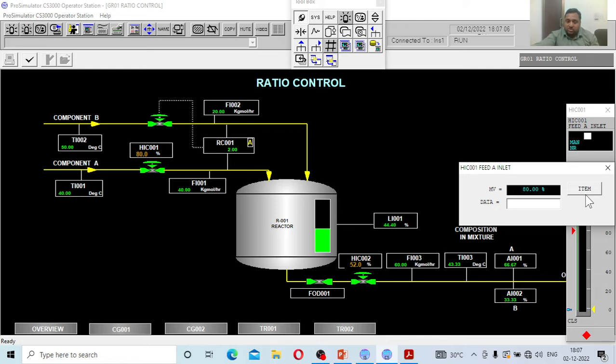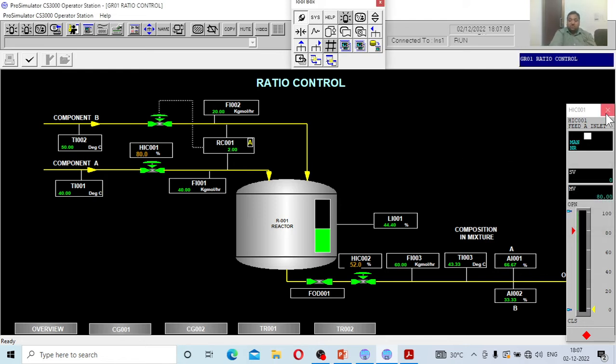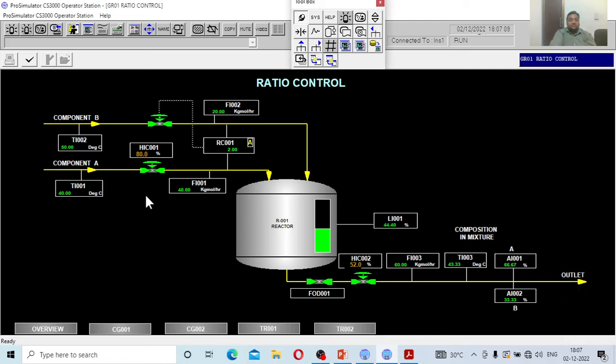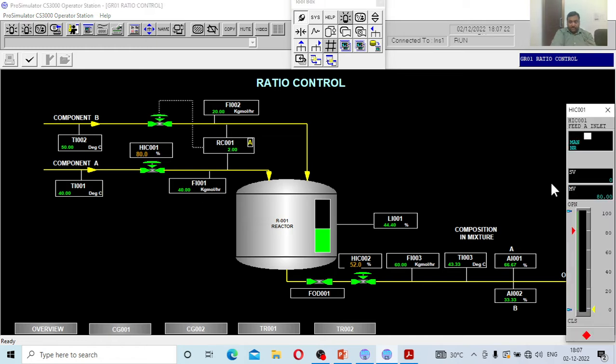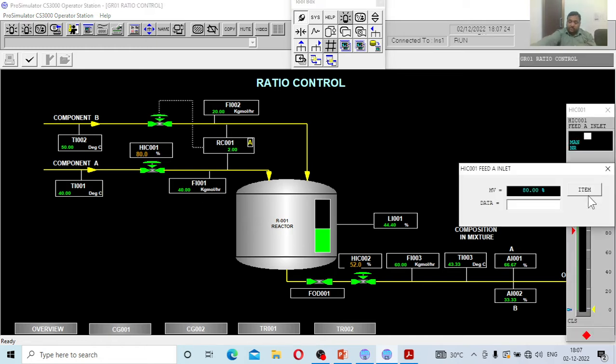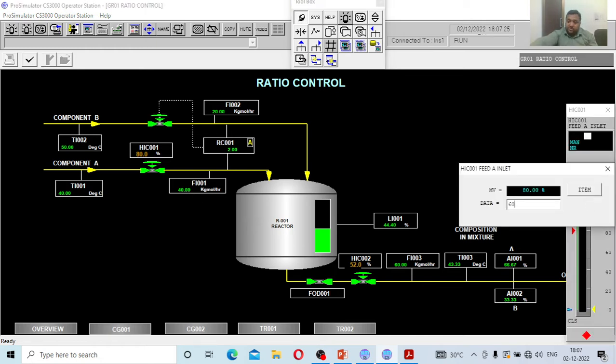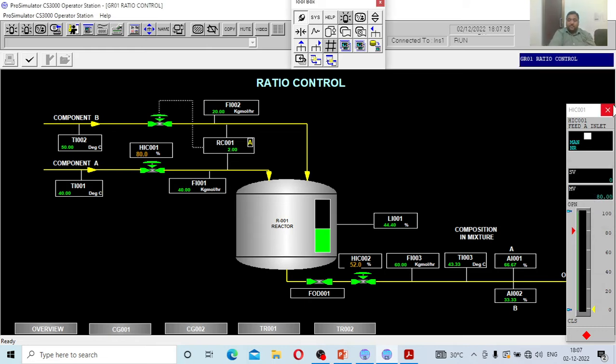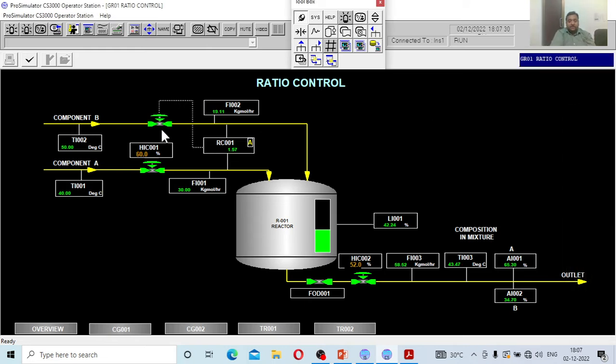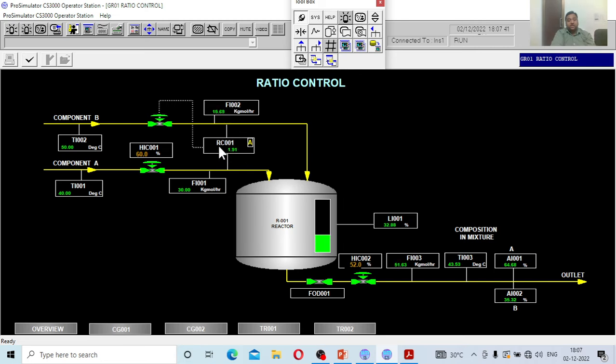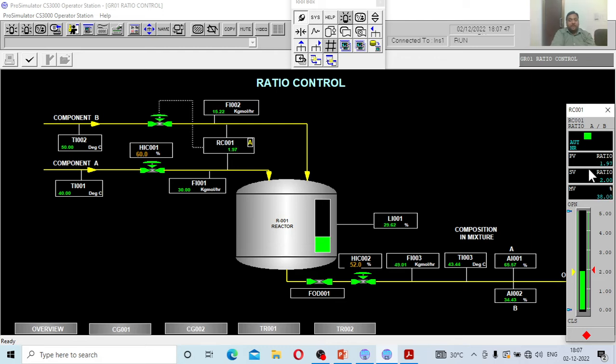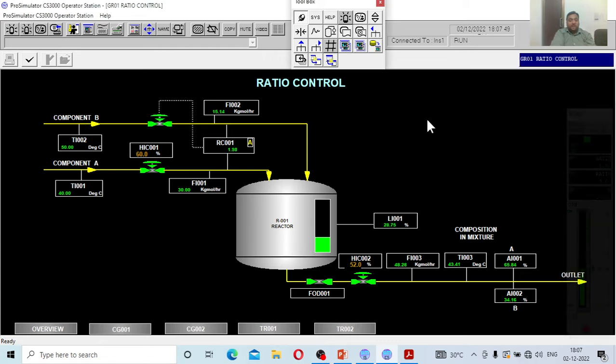What do you have to observe? Whether it is maintaining the same percentage, whether if I reduce A, is the amount of B also getting reduced stoichiometrically through the ratio controller. Let me reduce to 60 percent and see each parameter. The flow rate of A has been reduced to 30, accordingly it should be 15. The set point is 2, the process value is 1.95. Now it got disturbed, immediately it will bring B also to the stoichiometric amount which is 15.